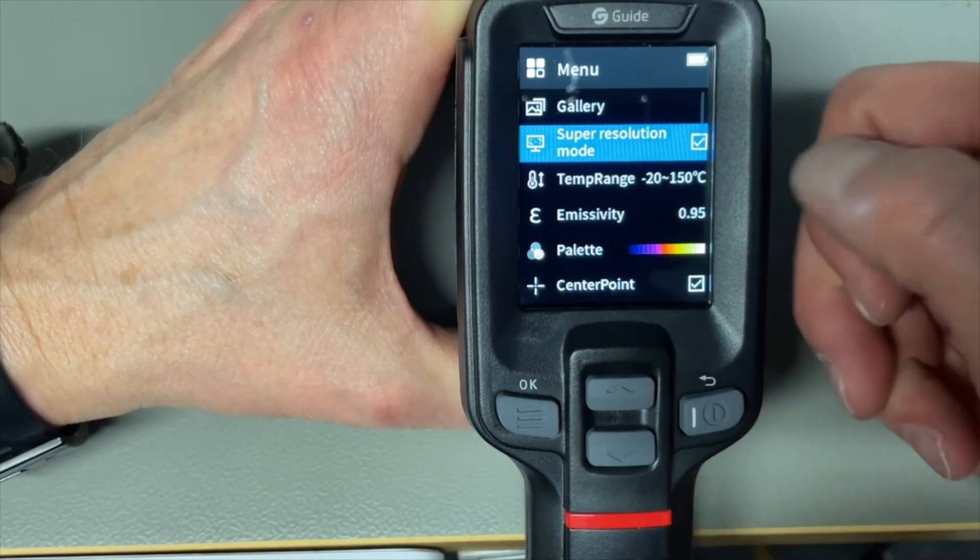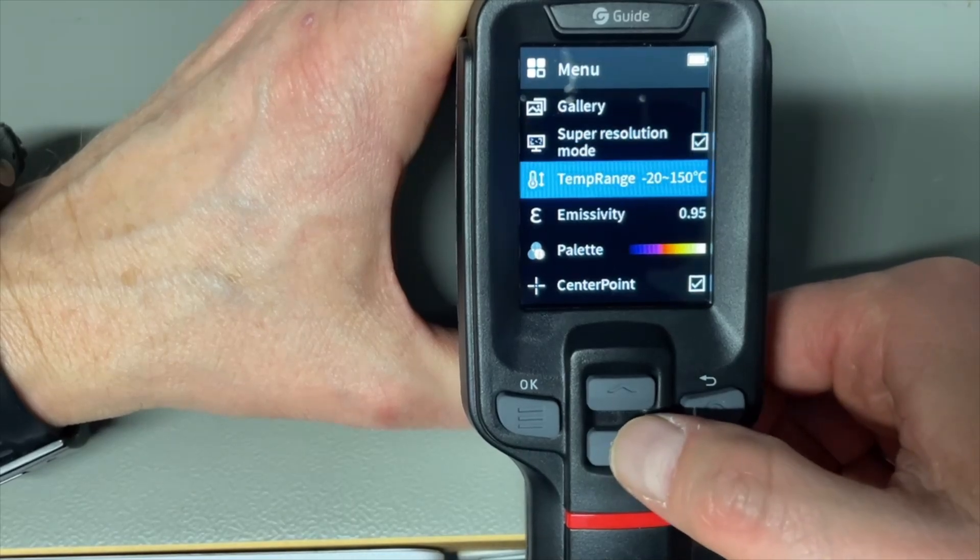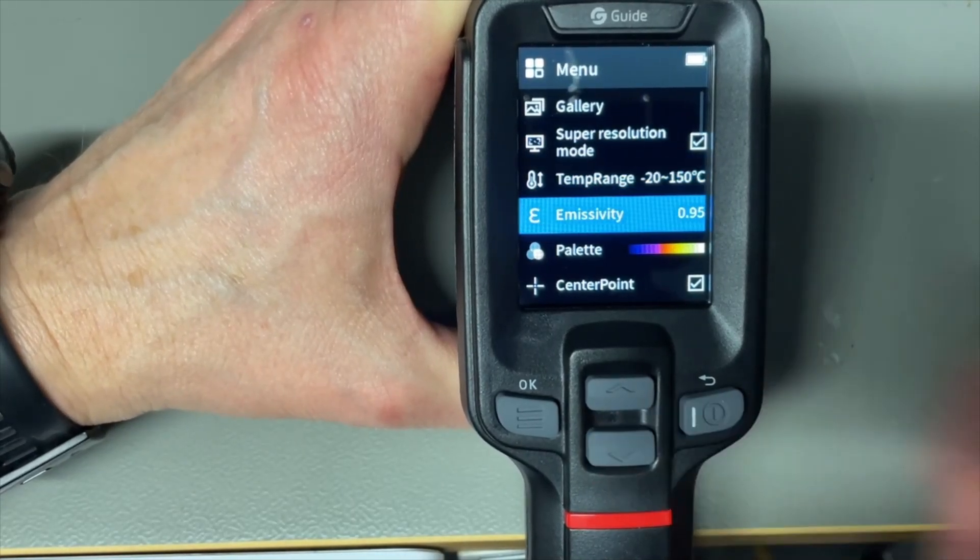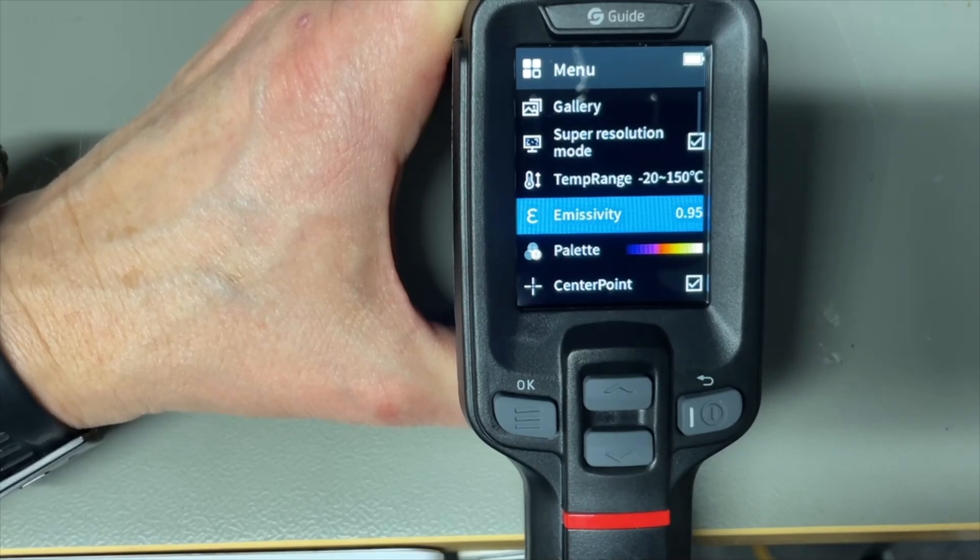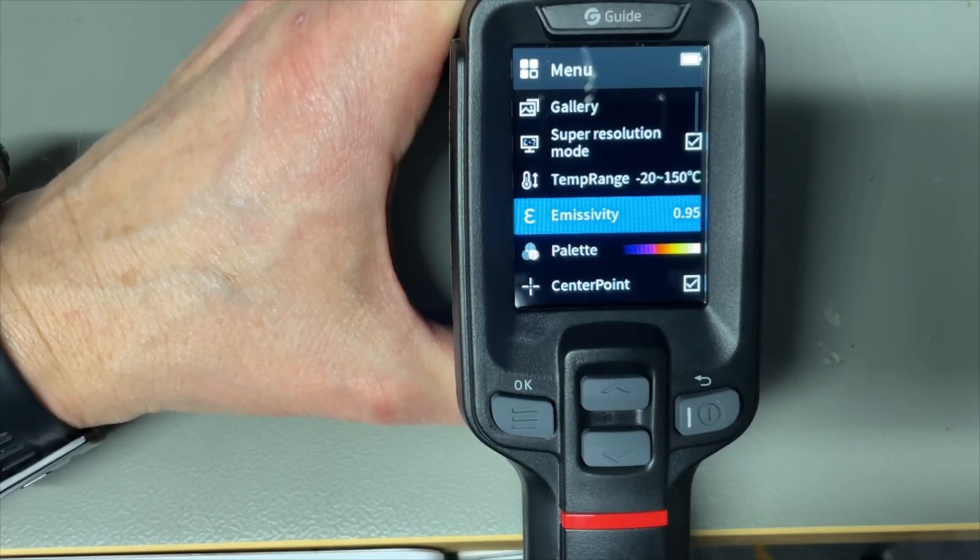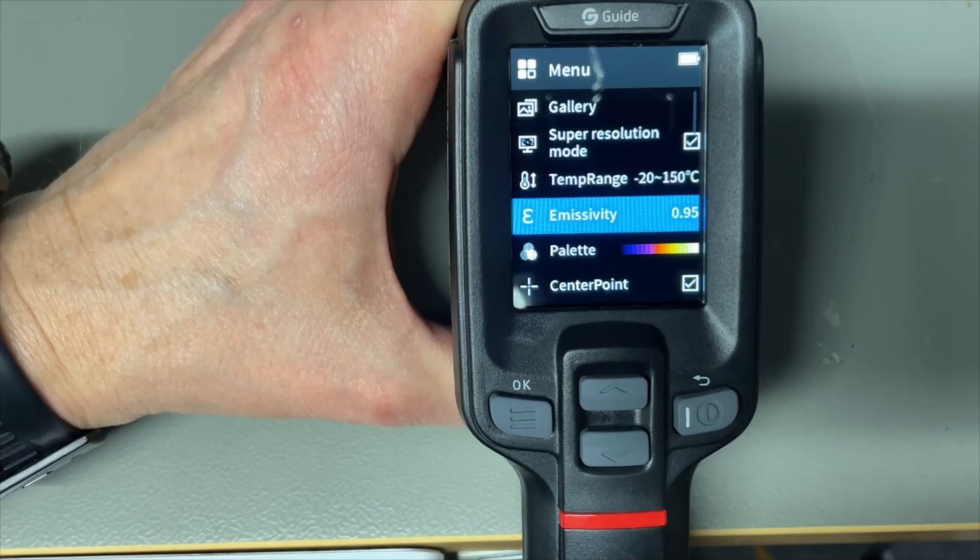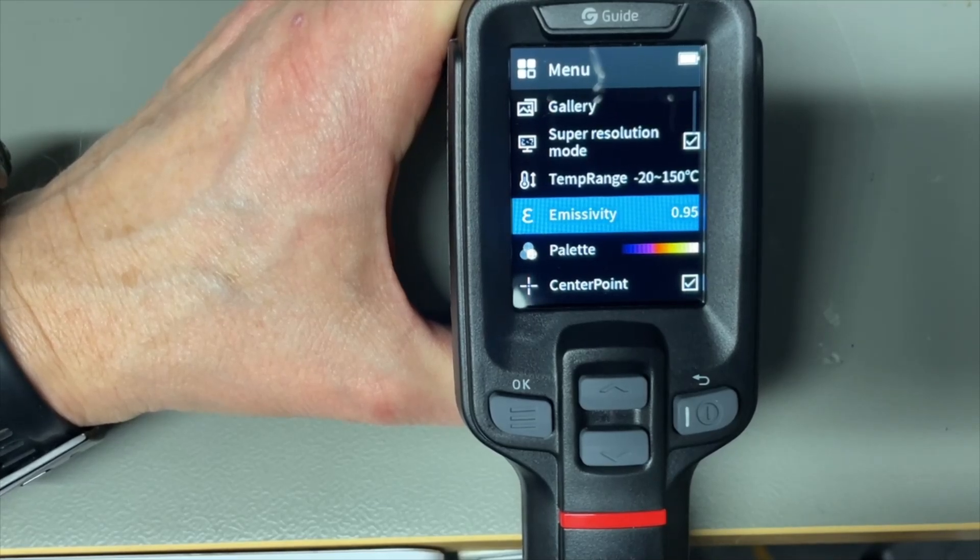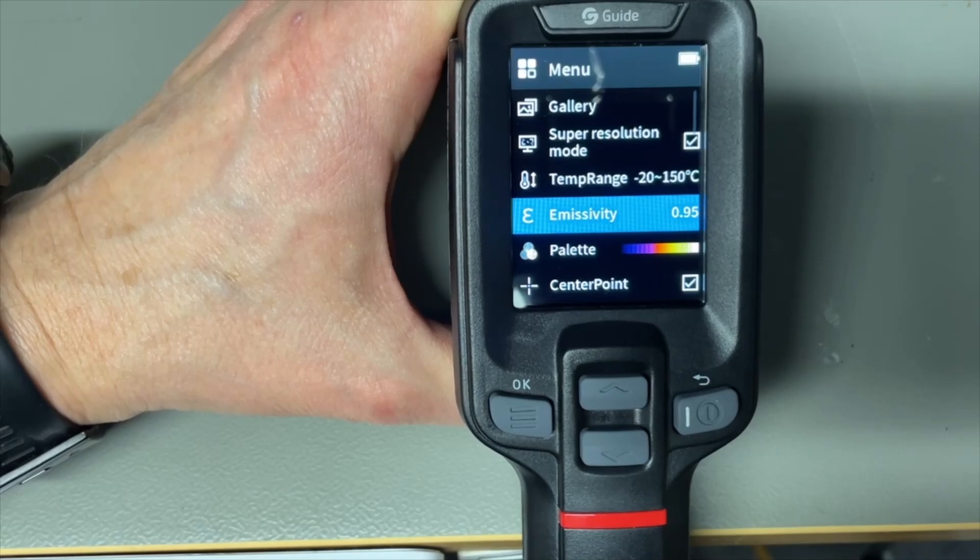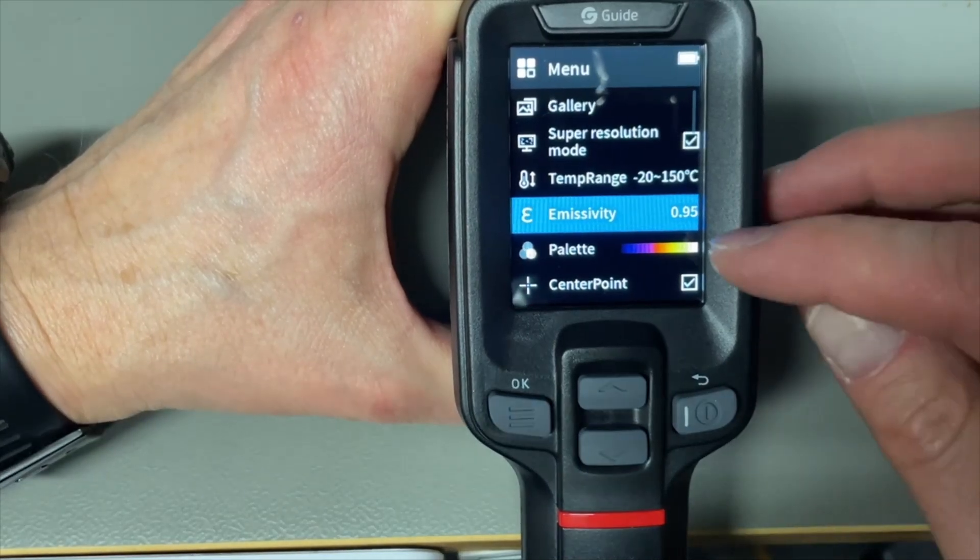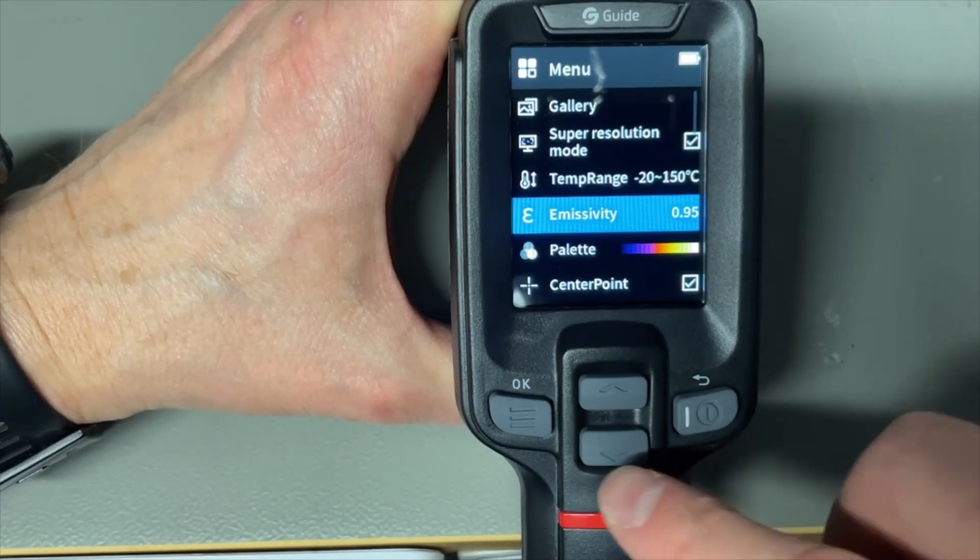The super resolution mode is switched on. The temperature range we have the emissivity. Different type of objects and materials have a different reflection so the temperature could be different. Like for instance if you are trying to measure a mirror or aluminum or something that reflects more then you can change this setting. So for wood there is a table for that.